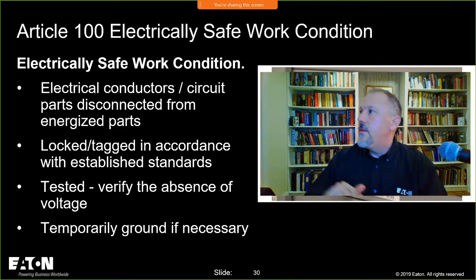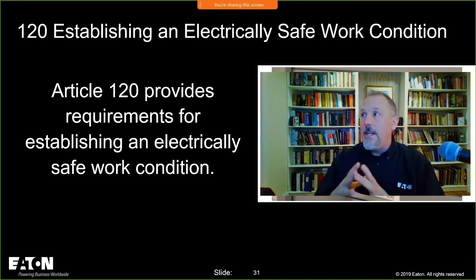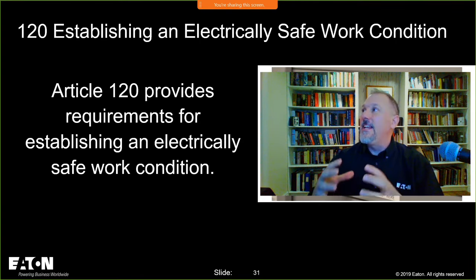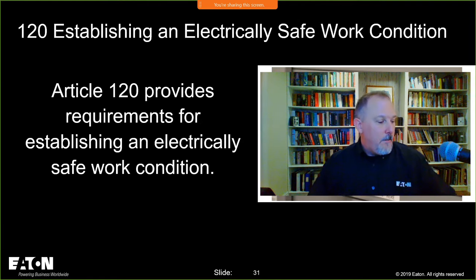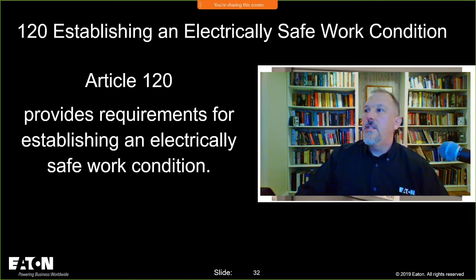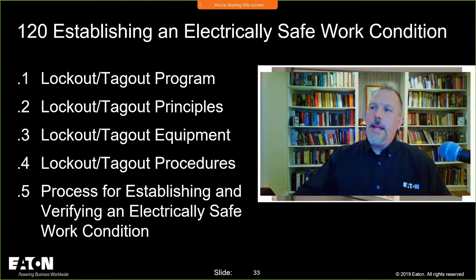In any case, it's really critical that we understand that we have a process to establish an electrically safe work condition. Article 120 is titled Establishing an Electrically Safe Work Condition. It's really important that we understand that 70E thinks it's so important that it gave it a whole article with its title, and Article 120 provides all of the requirements to establish that electrically safe work condition.